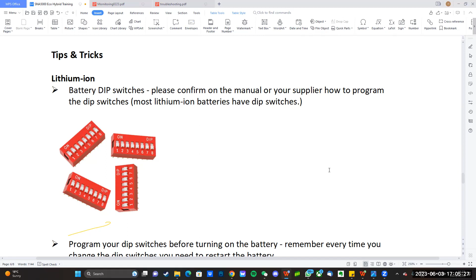For one or more batteries you'd have to program this. I know for some batteries like your Dyness, if it's one battery, you still have to program it. Program your dip switches before turning on the battery, and remember, every time you change dip switches, you need to restart the battery for it to take effect.